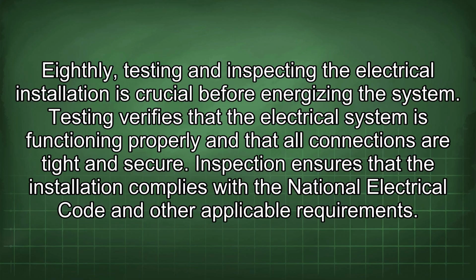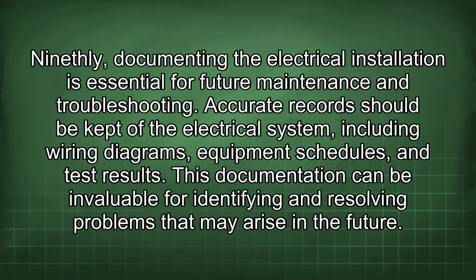Testing verifies that the electrical system is functioning properly and that all connections are tight and secure. Inspection ensures that the installation complies with the National Electrical Code and other applicable requirements. Ninthly, documenting the electrical installation is essential for future maintenance and troubleshooting. Accurate records should be kept of the electrical system, including wiring diagrams, equipment schedules, and test results. This documentation can be invaluable for identifying and resolving problems that may arise in the future.